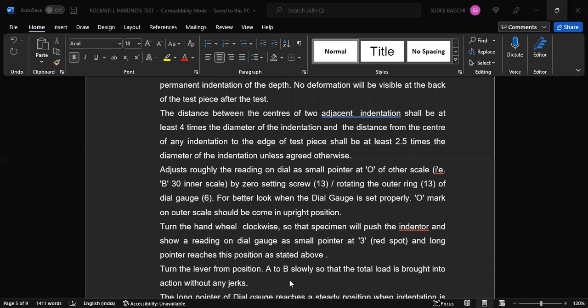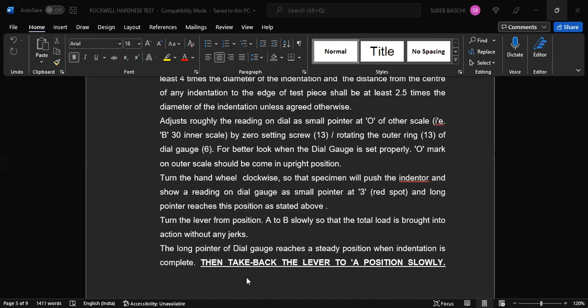Now turn the lever from position A to B slowly, so that the total load is brought into action without any jerk. The long pointer of the dial reaches a steady position when indentation is complete. Then take the lever back to its original position slowly. The lever should not go back suddenly, but should be taken back over a certain time.